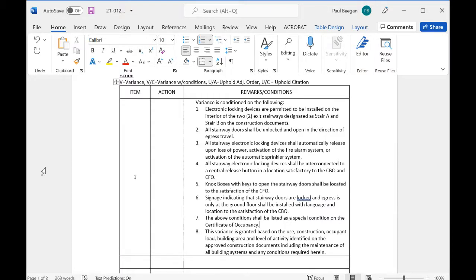Number three, all stairway electronic locking devices shall automatically release upon loss of power, activation of the fire alarm system, or activation of the automatic sprinkler system. Number four, all stairway electronic locking devices shall be interconnected to a central release button in a location satisfactory to the chief building official and chief fire official.